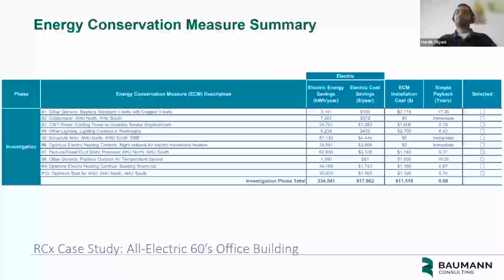So in this project, as part of the investigation phase, we were able to identify 10 ECMs, with a total of 334,000 kilowatt hours of annual energy savings, which had an implementation cost of $11,500. While there are a few ECMs that do have a simple payback of greater than 15 years, if we look at the overall payback for this entire project, it was less than 1 year. So that was a motivating factor for the client.